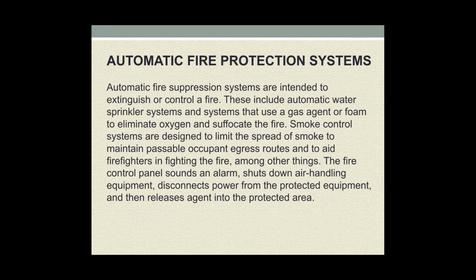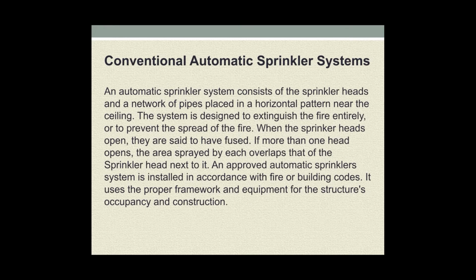Automatic fire protection system. Automatic fire suppression systems are intended to extinguish or control a fire. These include automatic water sprinkler systems and systems that use a gas agent or foam to eliminate oxygen and suffocate the fire. Smoke control systems are designed to limit the spread of smoke to maintain passable occupant egress routes and to aid firefighters in fighting the fire, among other things. The fire control panel sounds an alarm, shuts down air handling equipment, disconnects power from the protected equipment, and then releases agents into the protected area.